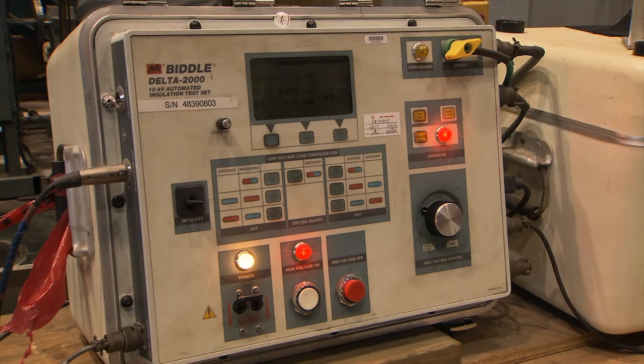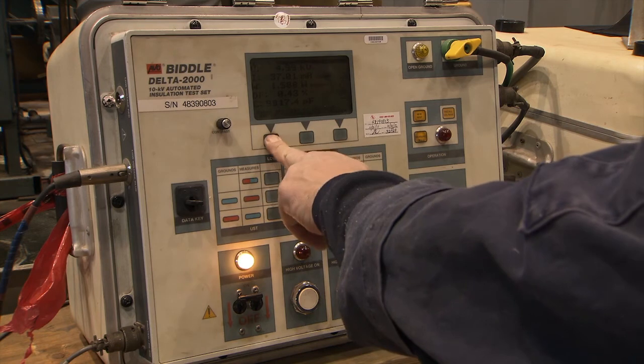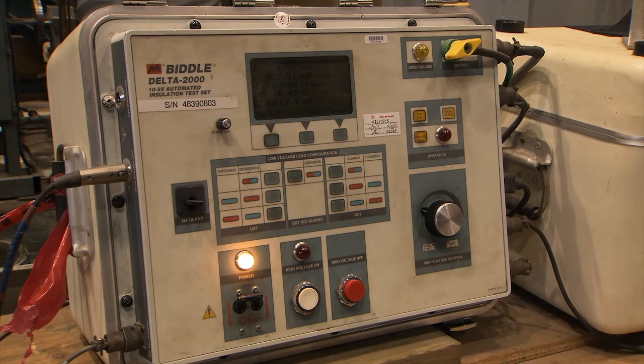The test is complete when a set of results appear in the display window, and the red operation light goes out, followed by the red high voltage light, indicating that the high voltage switch has shut off. Press the first button on the left under the digital display to print a copy of the test results.